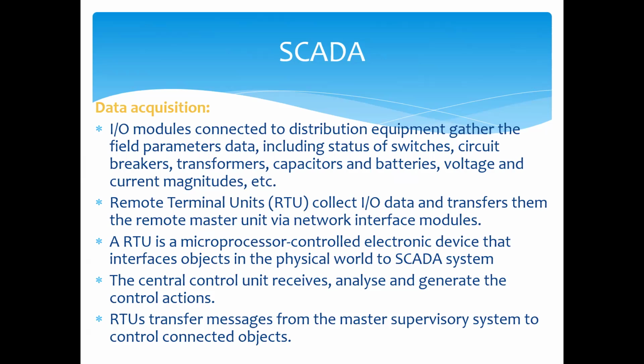For data acquisition in SCADA, input-output modules connected to distribution equipment gather the field parameters. What are the field parameters? Status of switches, circuit breakers, status of transformers, capacitors and batteries, and voltage and current magnitudes, like that. The remote terminal units collect input-output data and transfer them to the remote master unit via network interface modules. What's the RTU? It's a microprocessor-controlled electronic device that interfaces objects in the physical world to the SCADA system.